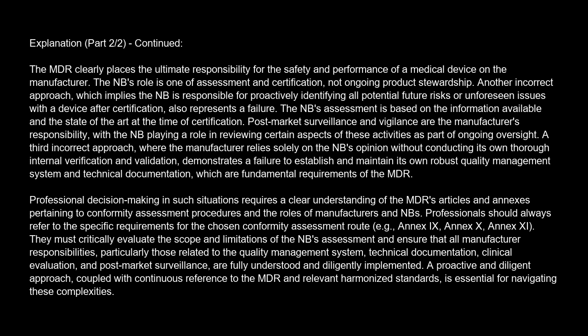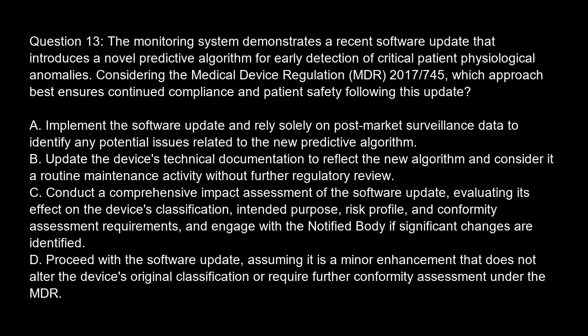Professionals should always refer to the specific requirements for the chosen conformity assessment route, e.g., Annex IX, Annex X, Annex XI. They must critically evaluate the scope and limitations of the NB's assessment and ensure that all manufacturer responsibilities, particularly those related to the quality management system, technical documentation, clinical evaluation, and post-market surveillance, are fully understood and diligently implemented. A proactive and diligent approach, coupled with continuous reference to the MDR and relevant harmonized standards, is essential for navigating these complexities. Question 13.